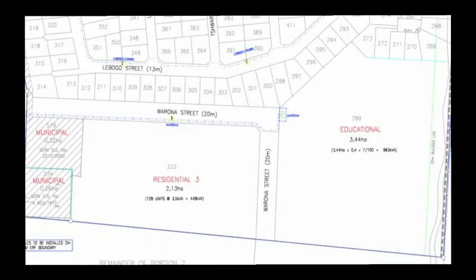So, based on those factors, you work out a kVA. For example, in this particular case, we'll take the RES 3 and the educational as an example. The RES 3, we've got 128 units allocated to this piece of ground. That's the density that the town planner and the developer has proposed, which ties in with what the city council wants. The type of development likely to happen in an area like this would be, we would allocate roughly 3.5 kVA per dwelling unit.